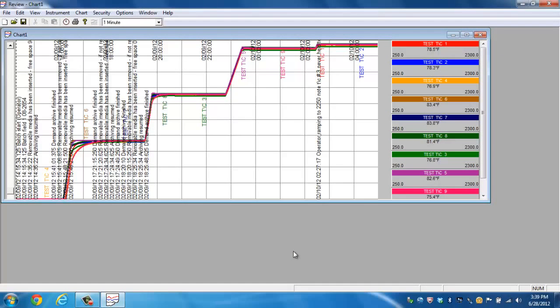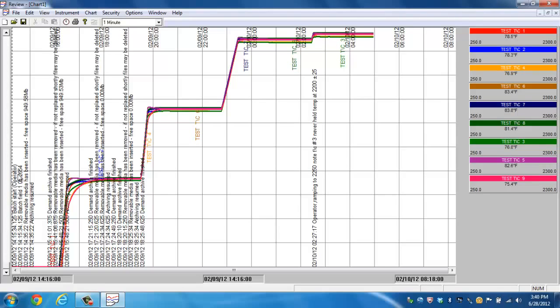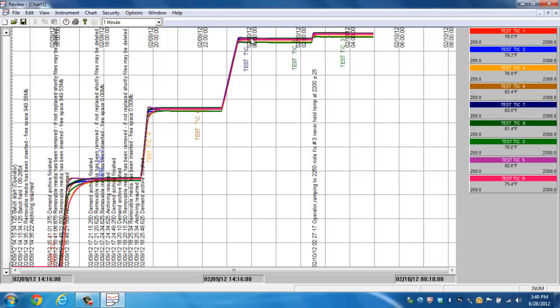It automatically rescales the chart to show you the very start of the batch data followed by the very end of the batch data. Let's go ahead and expand this a little bit more. So on the very far left hand side, you can see that we've got a date and a time and a message that says batch start by operator. It looks for a certain period of time, the furnace that this was monitoring was running at idle or room temperature. And then we started to ramp up to the first set point, followed by the second set point, followed by the third set point. So simply by looking for a specific batch name now, we can pull this information up. And then again, we are reviewing this data. This is one of the benefits of using review.